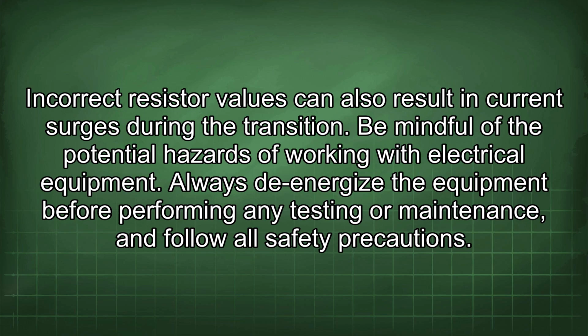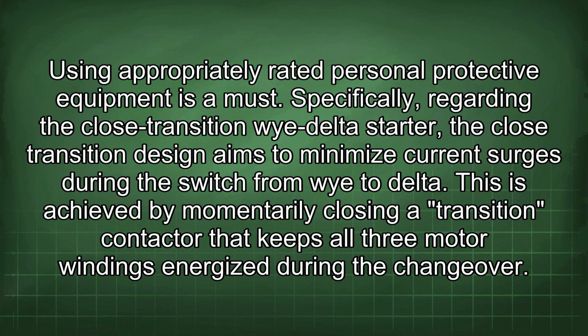Be mindful of the potential hazards of working with electrical equipment. Always de-energize the equipment before performing any testing or maintenance, and follow all safety precautions. Using appropriately rated personal protective equipment is a must. Specifically regarding the closed transition Wye-Delta starter, the closed transition design aims to minimize current surges during the switch from Y to Delta.